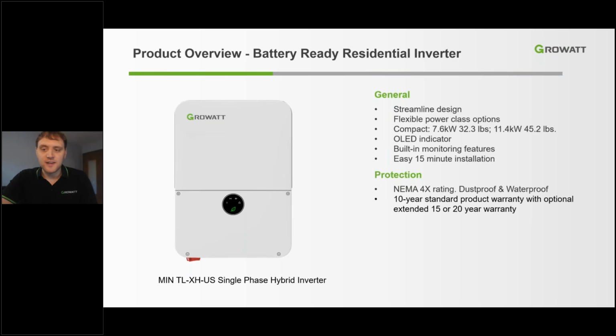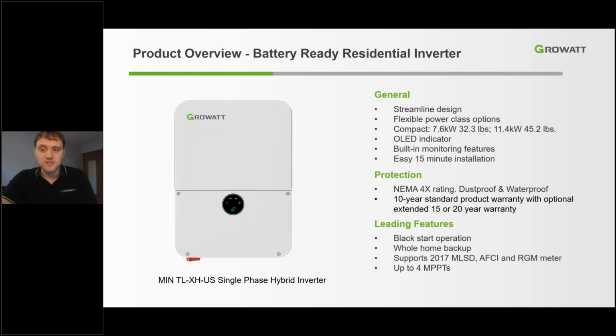The product has a built-in production and PV string monitoring, is very easy to install, and features a 10-year warranty, which can be extended to 20 years to follow the life of the PV array. The product can be installed and commissioned in as little as 15 minutes to save the installer's resources during many product installations, and can be installed indoors or outdoors according to our NEMA 4X rating.